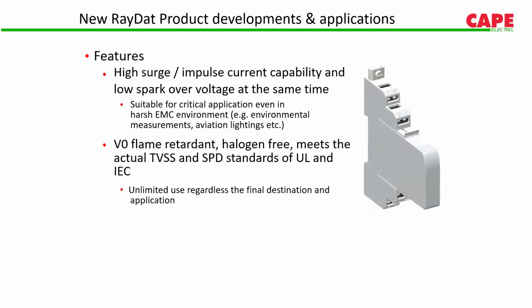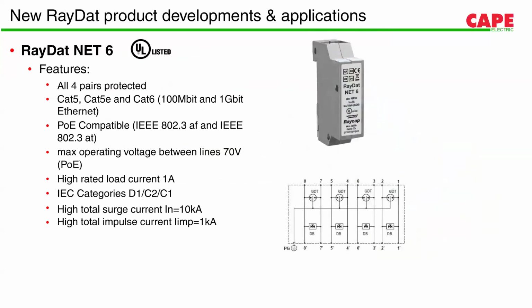Then we have data SPDs. These are signal SPDs for RS-485 communication systems. This comes in two-wire as well as four-wire communication systems. These are SPDs for Ethernet devices, for cameras and especially for network switches in data centers and so on. Wherever in industries I have been for any audit or discussion, one thing I have seen is that CCTV and network switches have always failed.